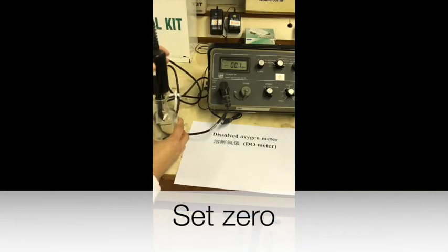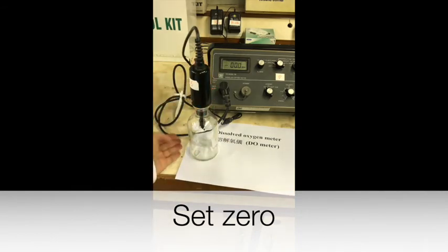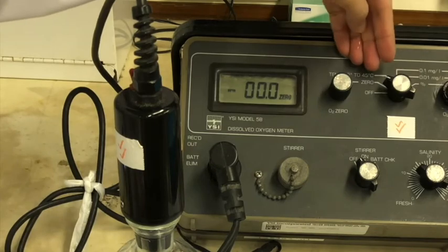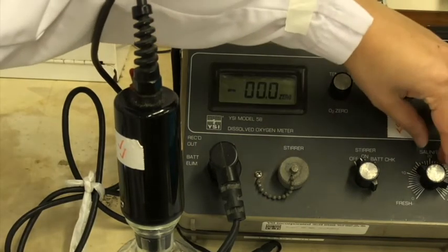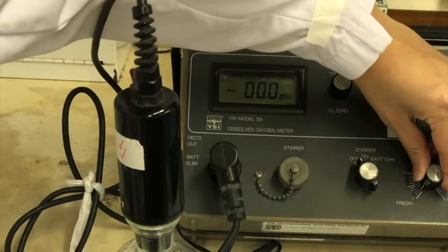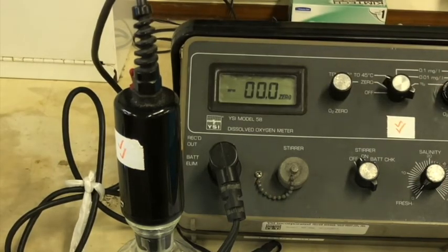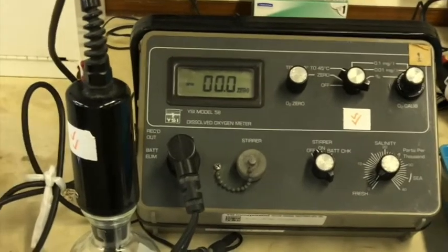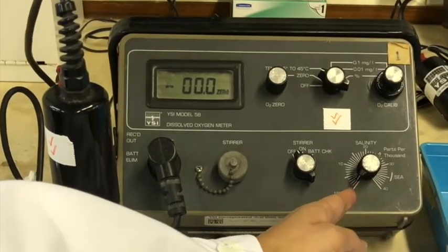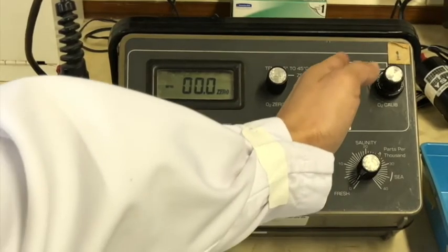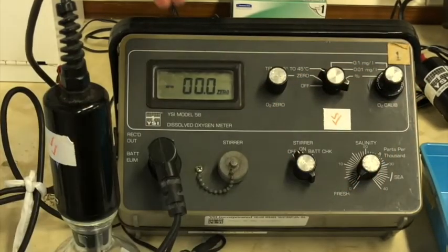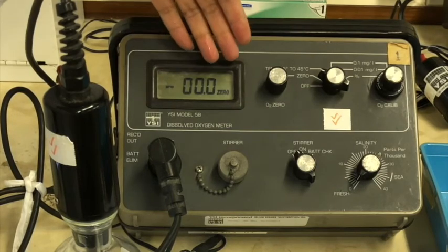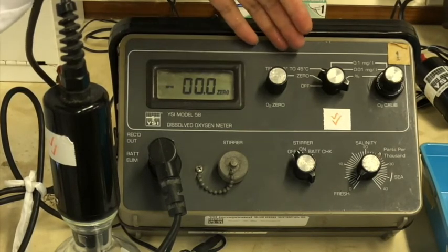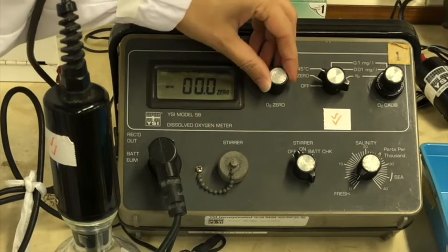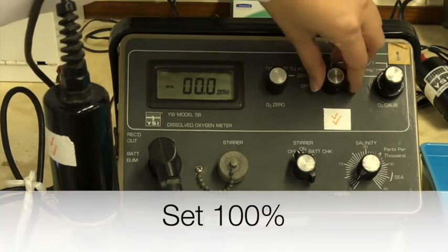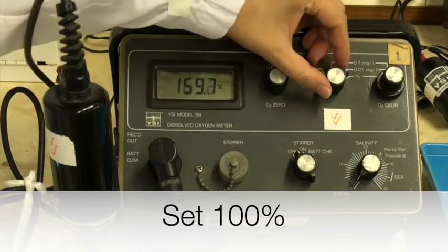For setting 0, place the electrode into an empty BOD bottle. Set the function switch to 0. Check that the salinity knob is set at 0. As there's no water inside the BOD bottle, salinity should be 0. When the salinity knob is set at 0 and the function switch at 0, adjust the display to reach 0.00. Set the function switch to percentage mode.